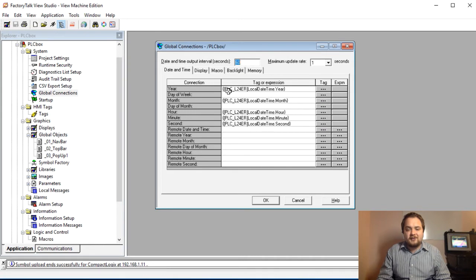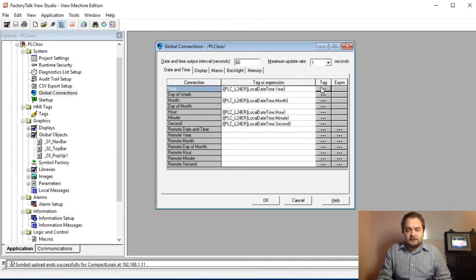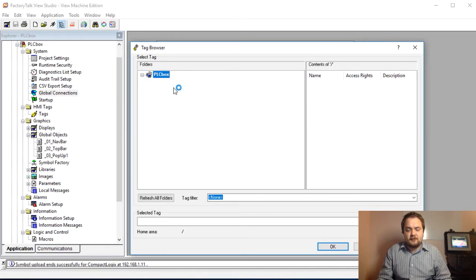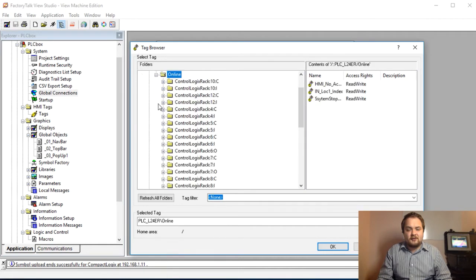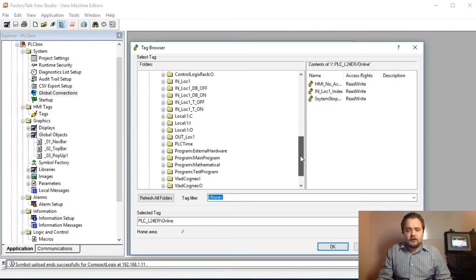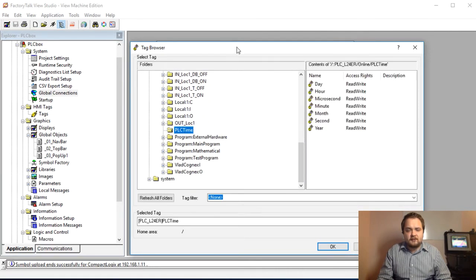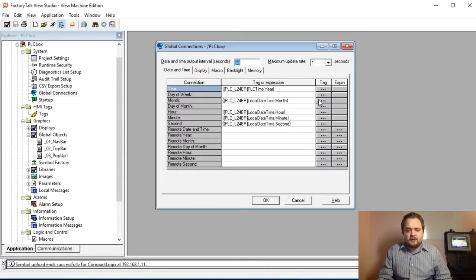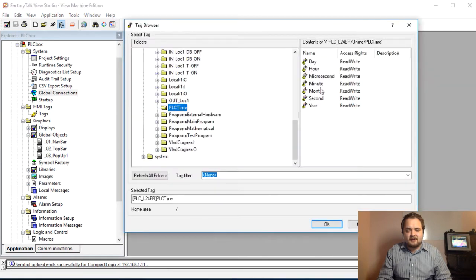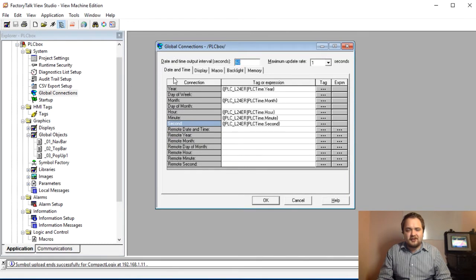The PLC_L24ER is already linked in my program through RSLinx Enterprise. You refresh all of these tags, then under PLC_L24ER expand the section and find the online tags. We can find PLC_Time right there — we select PLC_Time dot Year and hit OK. You do this for all fields: month, hour, minutes, and seconds. That's how you sync your timer — in the Global Connections, Date and Time tab, hit OK.